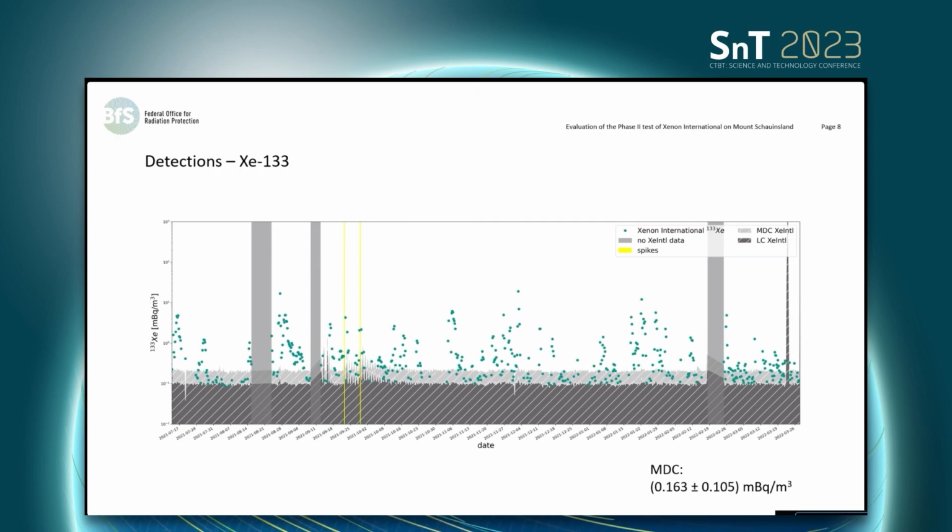Just not to trust some of the measurements right after the spike, because there was a little bit of an issue with the detector coating not working perfectly well. So we do have some memory effect here, as you can also see in this MDC, which looks like it's oscillating after the spikes. That's just because some of the detectors were coated very well, and others had a little problem with the coating. And there you can see this memory effect.